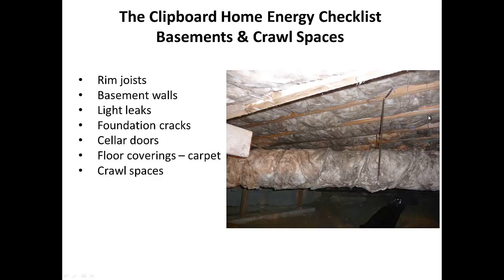And if you've got a pipe running through here, what you've done by insulating is you've taken that pipe that was relying on the heat coming from up above to keep it from freezing, and now you've reduced that water pipe that runs down through here so that it's not going to be warm anymore. And so it's going to freeze, and you're going to have a broken pipe. So whenever you can, you may need to take some of those copper pipes and move them up into the cavity and then put the insulation over top of it. So just be aware that you can cause a problem by doing something good. You can cause a problem with your pipes if you insulate and don't protect the pipes that are in there.